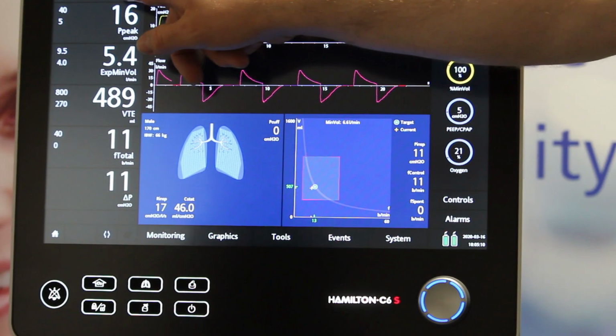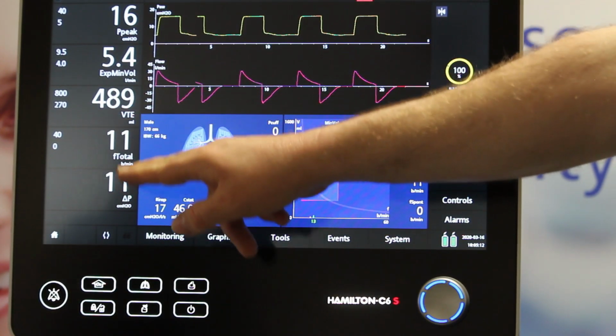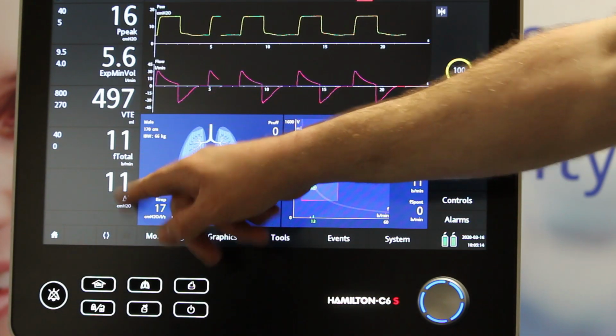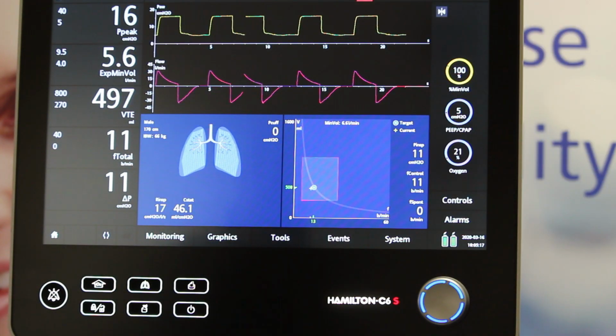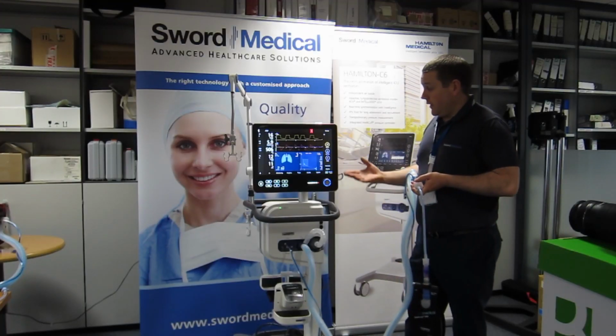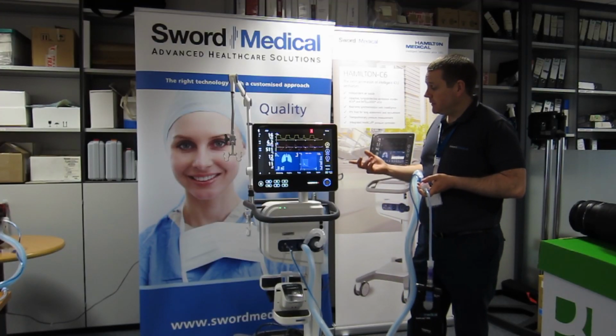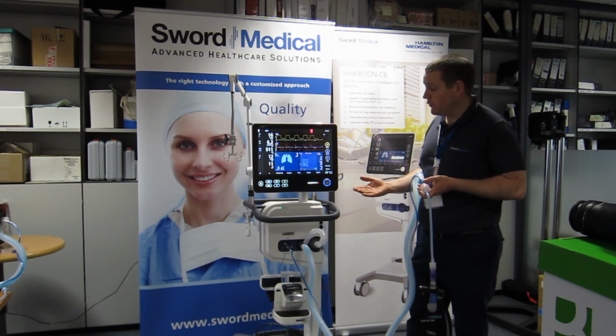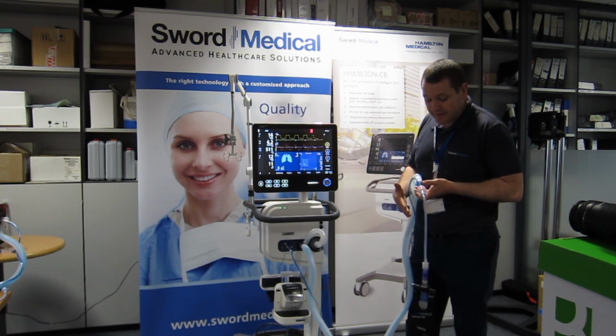We've got the mode that we're on here. We've got the main monitored parameters here. Drawing your attention to this one. So Hamilton ventilators have the driving pressure as a monitored value. So I've done nothing, only put in my height, press start, and the ventilator has taken over and is now appropriately ventilating this lung.